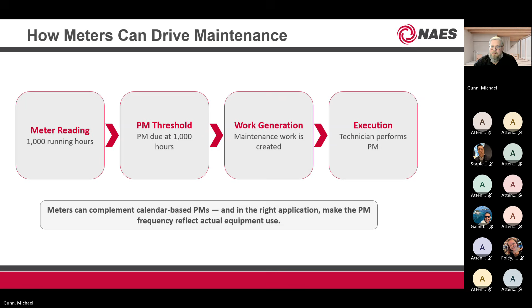Some examples and best practices are pumps. I'm trying to think of how many times I've seen pump PMs generate work orders. It hasn't been too much, but there is a case for that based on run hours and how many times you start that pump. That can drive when lubrication or other inspections are needed, and when you need an overhaul. Overhaul is probably the most common example of run hour based maintenance on something like a pump. Once you get to, I don't have an exact number, but 30,000 or 20,000 hours is generally where we're tracking those meters, and once we hit a certain threshold is where we want to look into overhauling that pump.